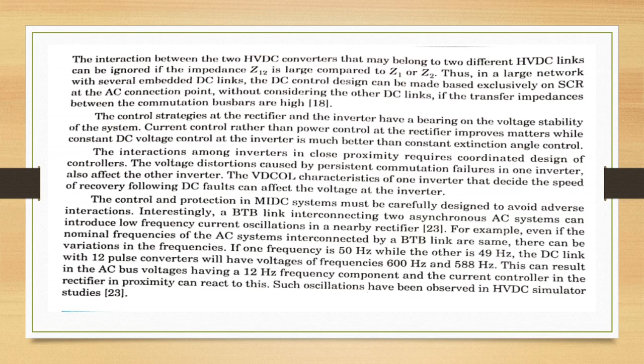Control strategies at rectifier and inverter have a bearing on the voltage stability of the system. Current control rather than power control at the rectifier improves matters, while constant DC voltage control at the inverter is much better than constant extinction angle control.